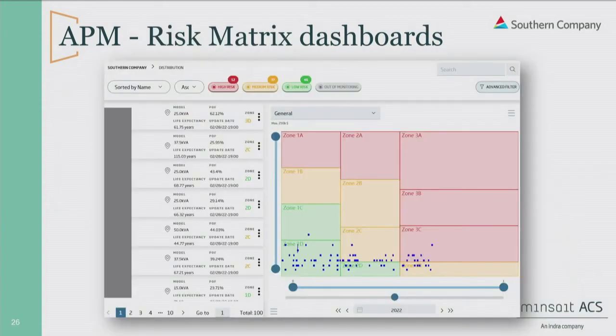And then we have a risk matrix. The cool thing about it is that just because I have a transformer showing a health alert, which is red, that doesn't mean it has a high risk of failure. So I can have a transformer that the health index says is about to fail, but when I look at my risk matrix, it's actually in this lower risk zone.